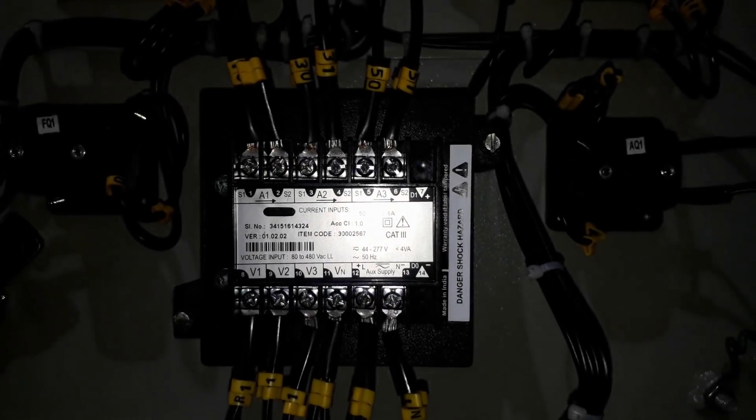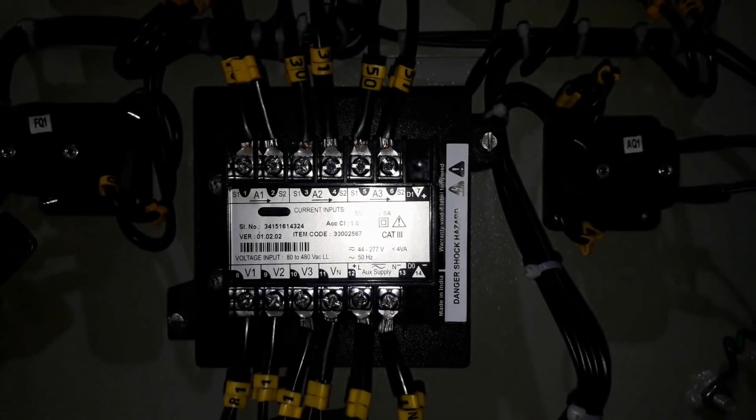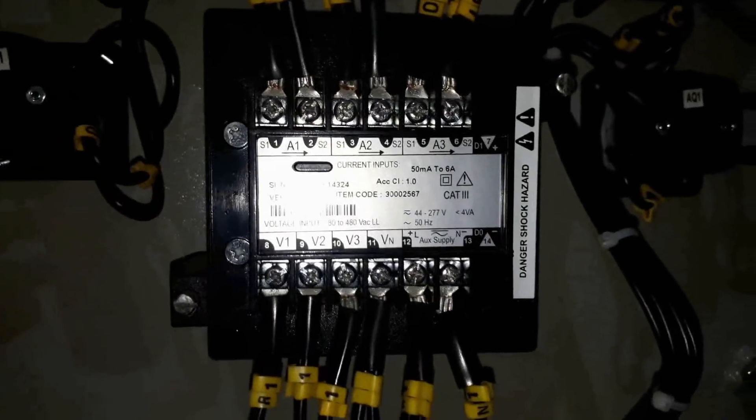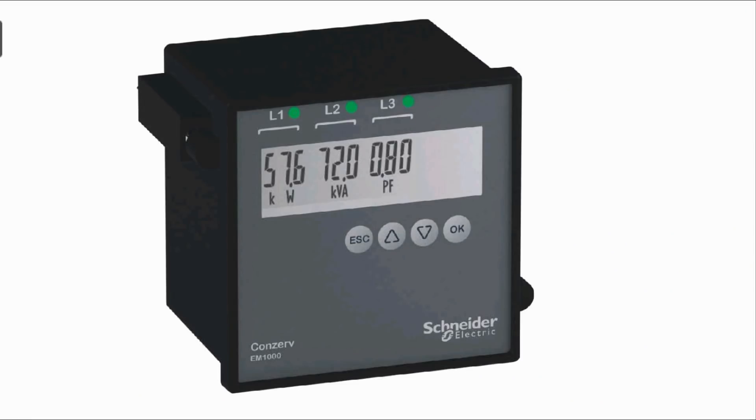The CT for line 1 — S1 and S2 of that CT — are connected to A1 S1 S2, and similarly for A2 and A3. On the bottom side you can see V1, V2, V3, and VN terminals, where the three phases and neutral are connected. There is also a line and neutral terminal for the auxiliary control supply of 44 to 277 volt AC.